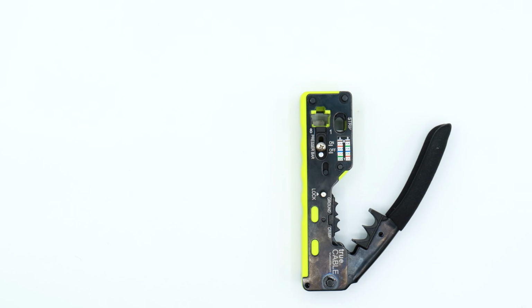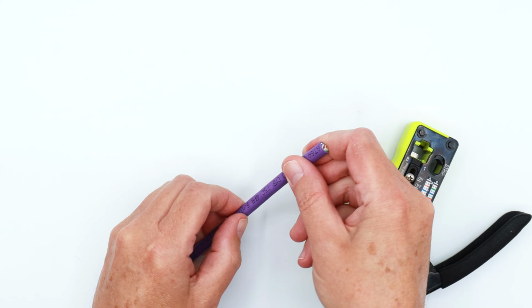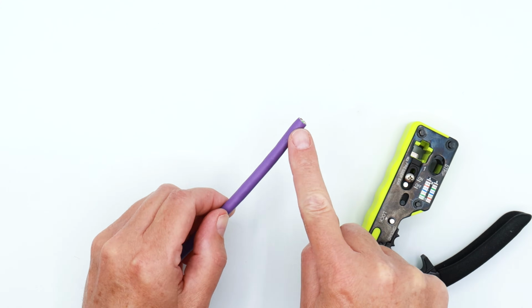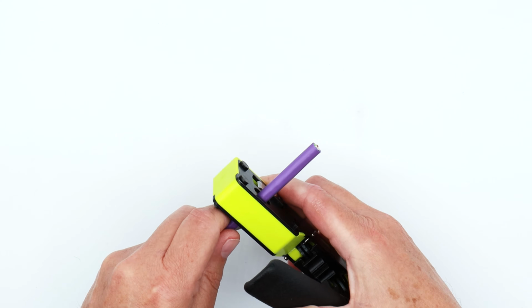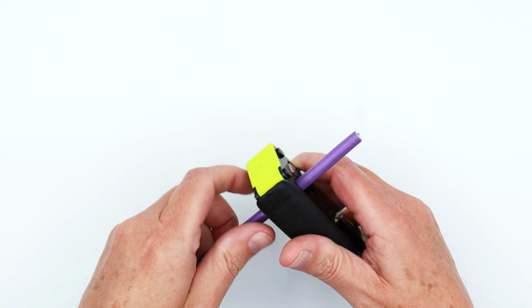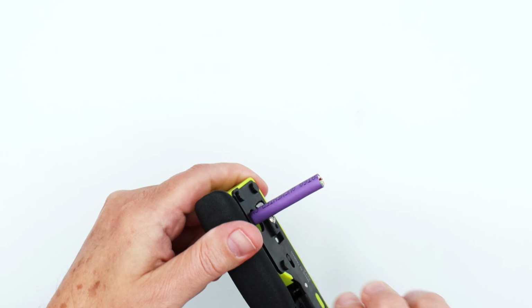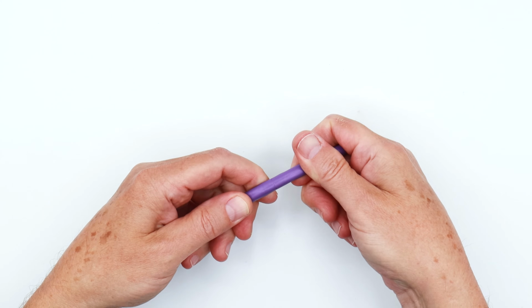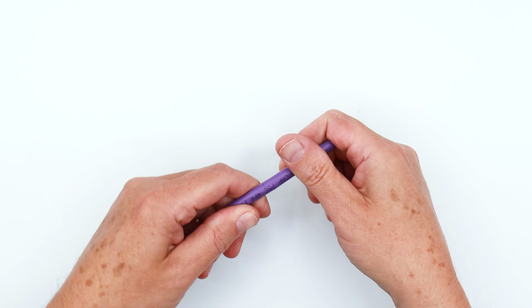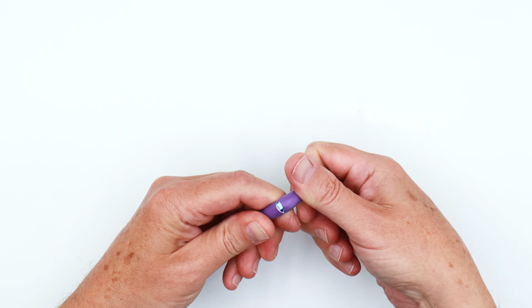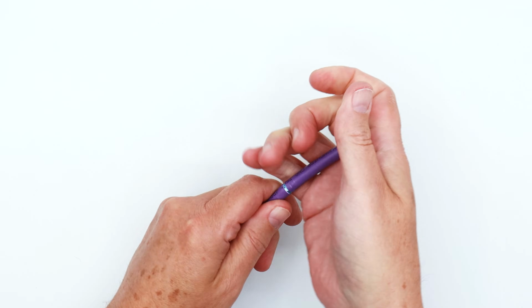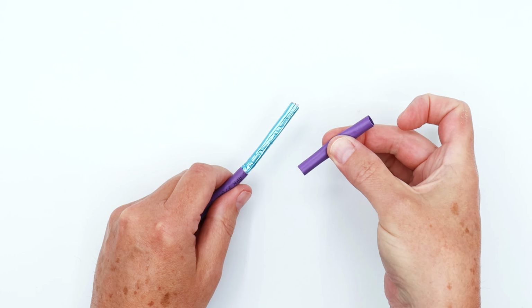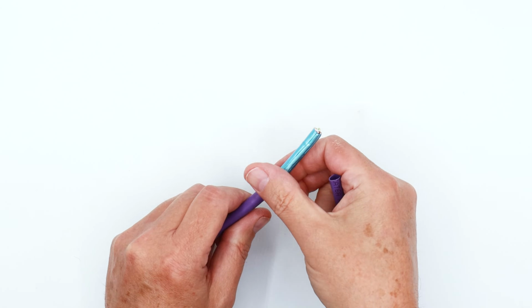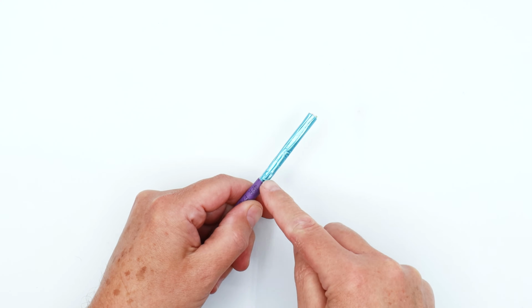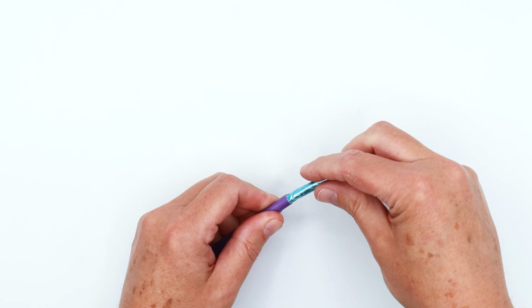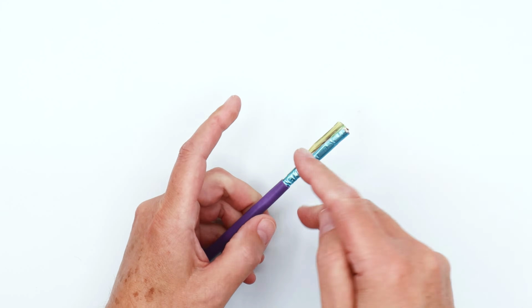So we're going to demonstrate category 6A plenum shielded, and it's a very thick cable. So we're going to strip about an inch and a half or so to 2 inches of cable jacket off of there. And you just simply turn the tool around one full turn. And what you're looking to do is put a nice score on there, which I did. You didn't actually cut through, you put a score. So you're going to pop on one side, you're going to pop on the other side, and then you're going to pull it off. So keep this around because this is going to come in handy to untwist your conductors. But as you can see, the stripper didn't cut through the cable shield, which is very important because if it does, you could have nicked a conductor and you have to cut off and start all over again.